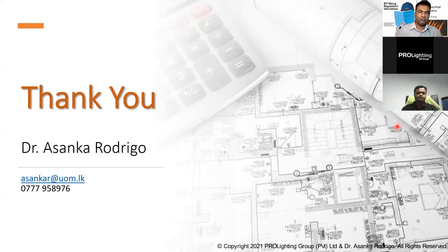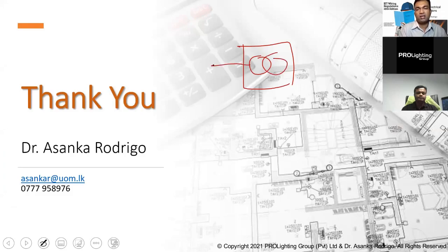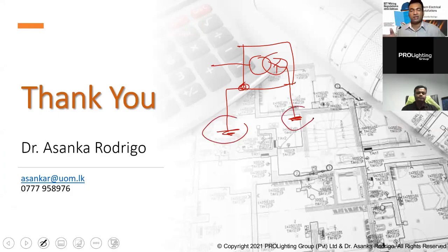For example, let me draw it here. Let's say you have a substation where your high voltage and low voltage sides are there, and here you have the neutral point. Now, when you look at the transformer body, there are different options available, depending on the requirement. Normally, in distribution transformers, what the CEB and LECO follow is maintaining two different earths, electrically separated, so that even if a fault happens on the high voltage side, it will not transfer to the low voltage side.